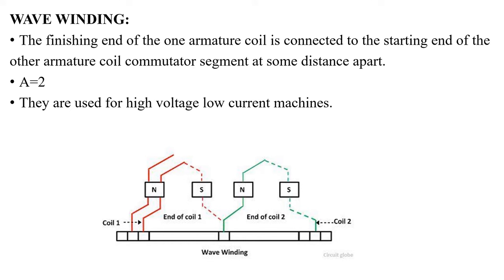Now let us see what is meant by wave winding. In wave windings, the finishing end of one coil is connected to the starting end of the next coil. In this diagram, the coil starts here, ends here, and the next coil starts from there. In wave windings, the number of parallel paths is always 2, whereas for lap windings the number of parallel paths depends on the number of poles. The number of poles is independent of the number of parallel paths in the case of wave windings. Wave windings are normally used for high voltage, low current applications.